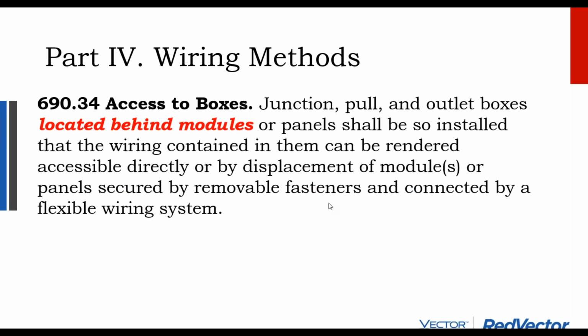Access to boxes. So when you go from the array into the building, you transition through a box. That box is allowed to be located underneath the array. And the reason why you'd hide the box underneath the array, even though it's slightly less accessible, is that it looks better and it's shaded and it's protected from the elements, from animals, from rain. And so you're allowed to put these junction boxes on the rooftop underneath the solar array, and high quality installers do, unless there's a compelling reason not to.